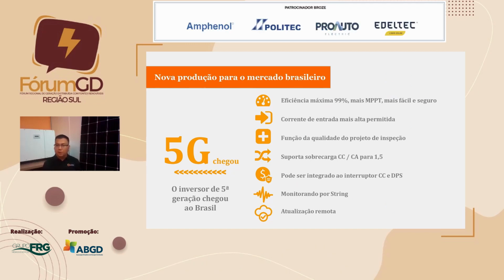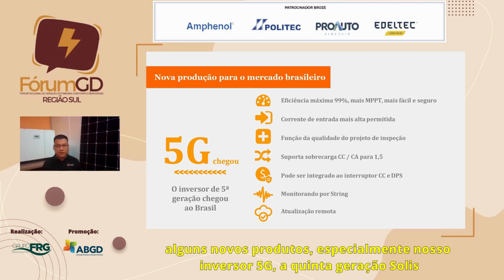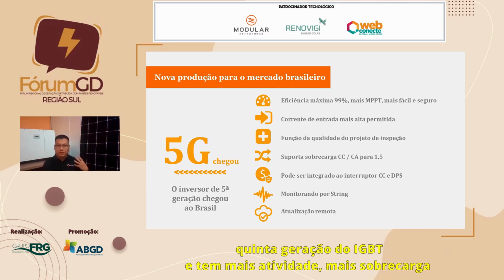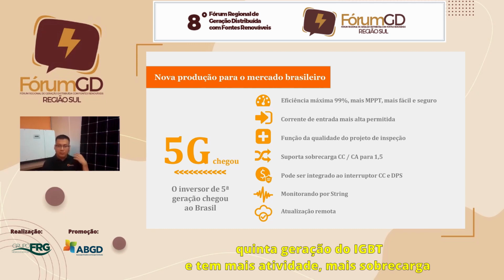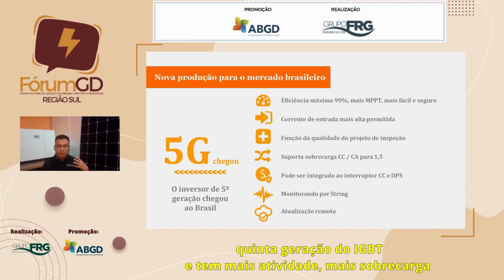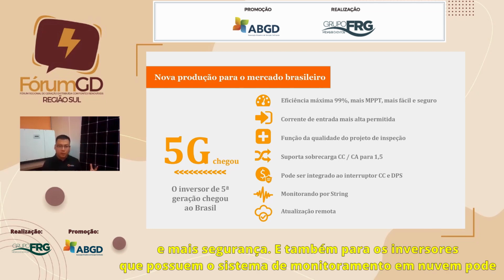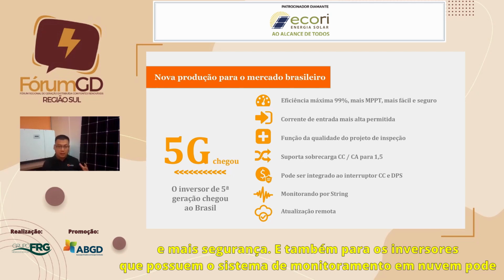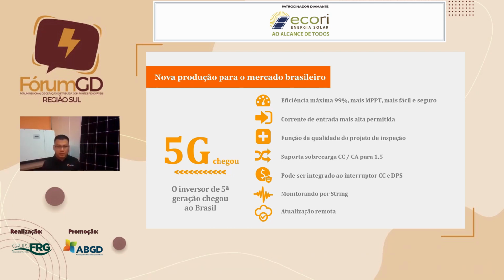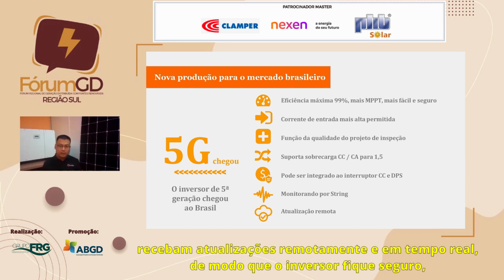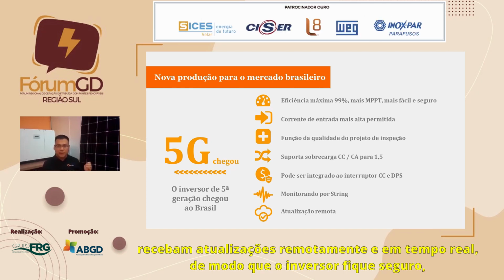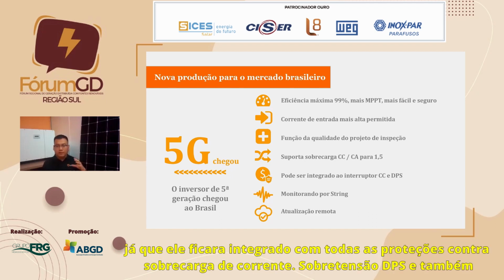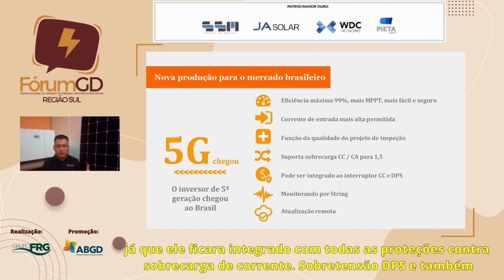So this year we have some new products, especially our 5G inverter, the fifth generation solar inverter. It uses the fifth generation IGBT, and it has more MPPT, more overload, and is safer. Also, the inverter has a cloud monitoring system that can monitor each string and update remotely. And the inverter is safe because it integrates all the protections like overcurrent, overvoltage, DPS, and also the interrupter.